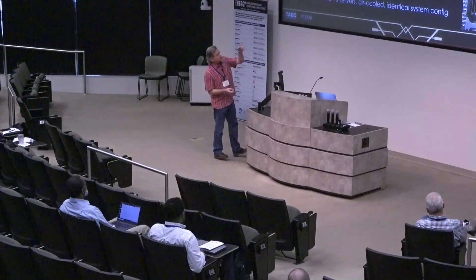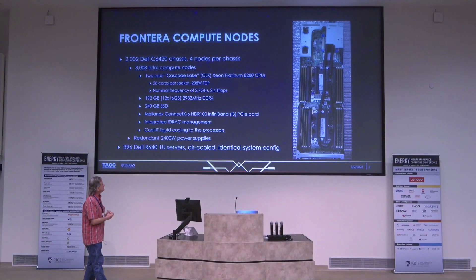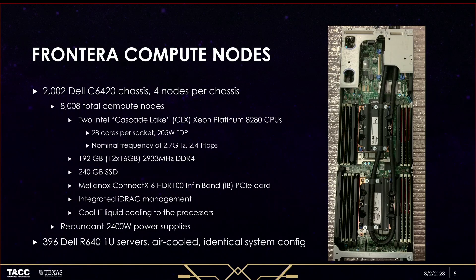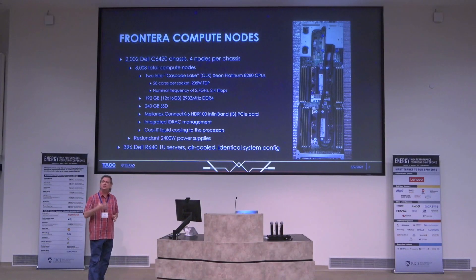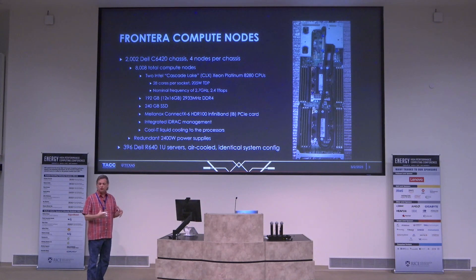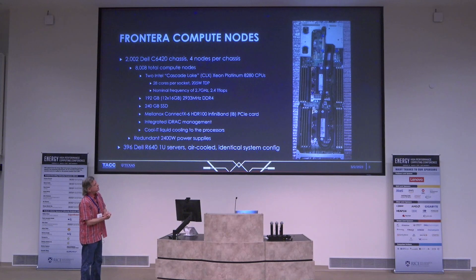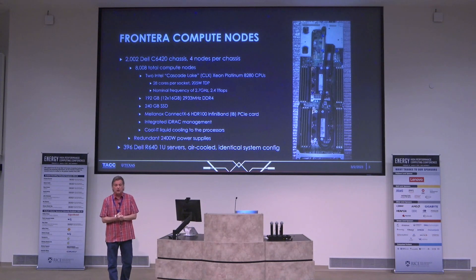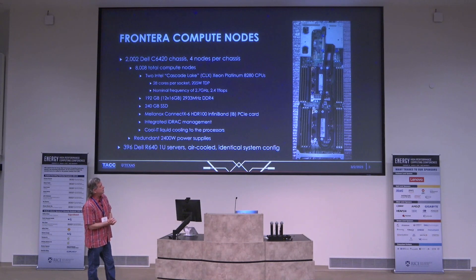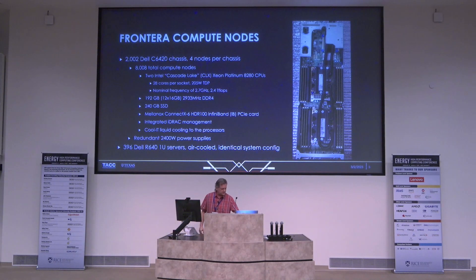We have cool-IT loops on the system that provide the bulk of the cooling. Since only the processors are liquid-cooled, there's still some other power inside the chassis requiring cooling, so we put chilled doors on the back. About 75% of the cooling comes from the direct liquid cooling and 25% from the chilled doors — about 15 kilowatts out of the chilled doors — making it room neutral. These are four nodes per chassis and they've been great workhorses. We also have AMD follow-on chassis as part of the Lone Star 6 system.